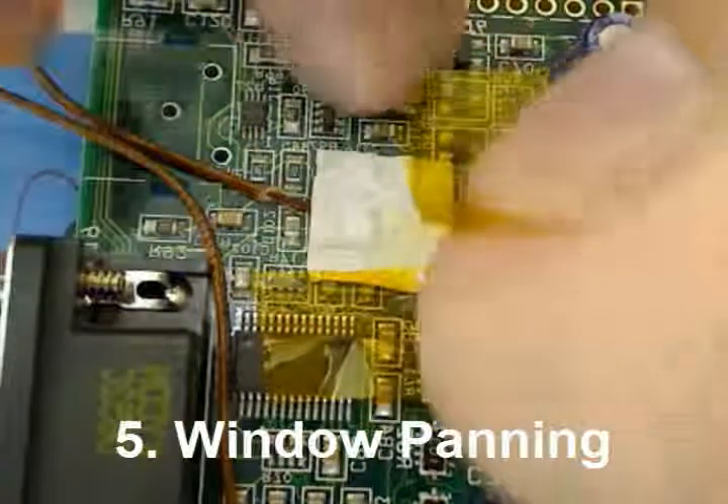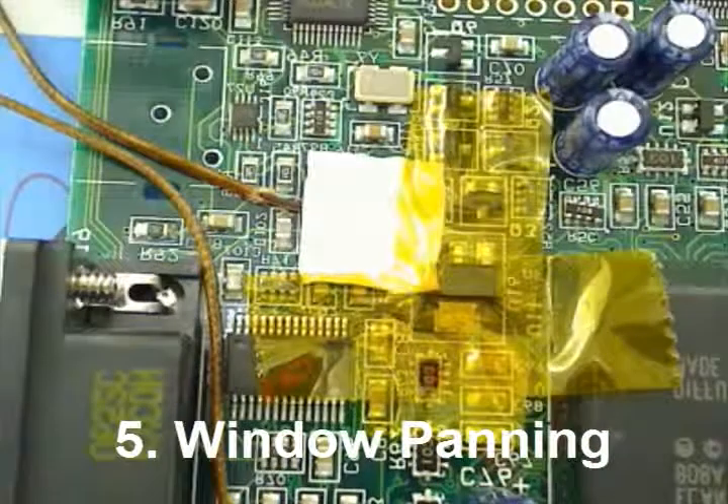For added life of your connection, Kapton tape can be applied. Here is a popular method of window panning. Notice you are not covering the actual thermocouple bead, as doing so will distort your thermal readings.